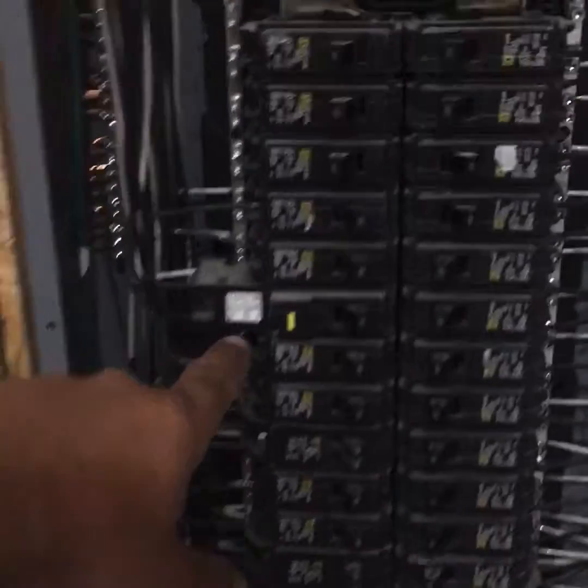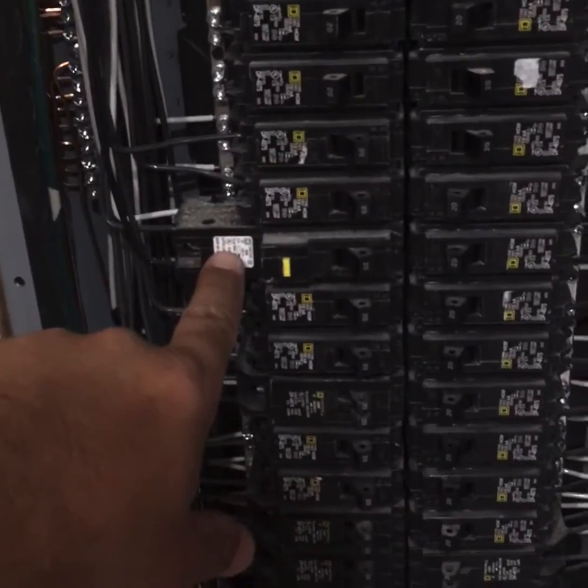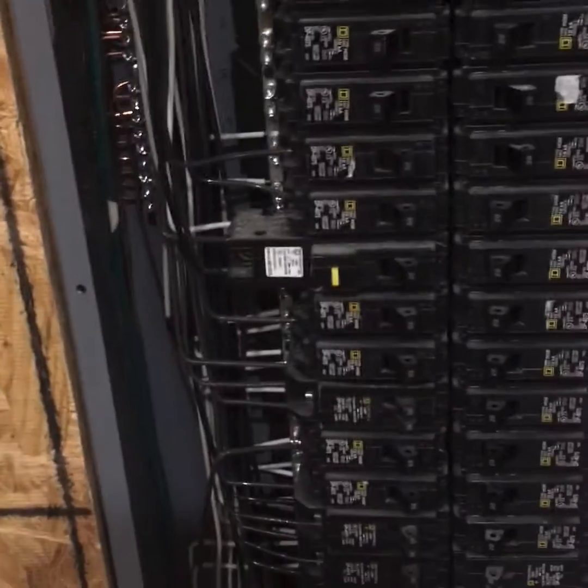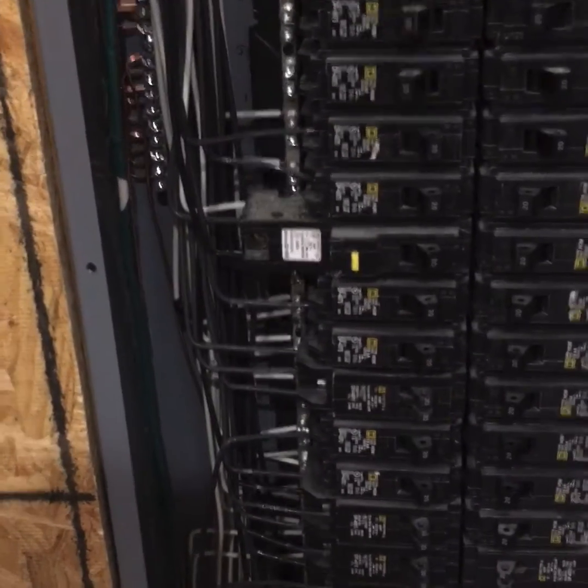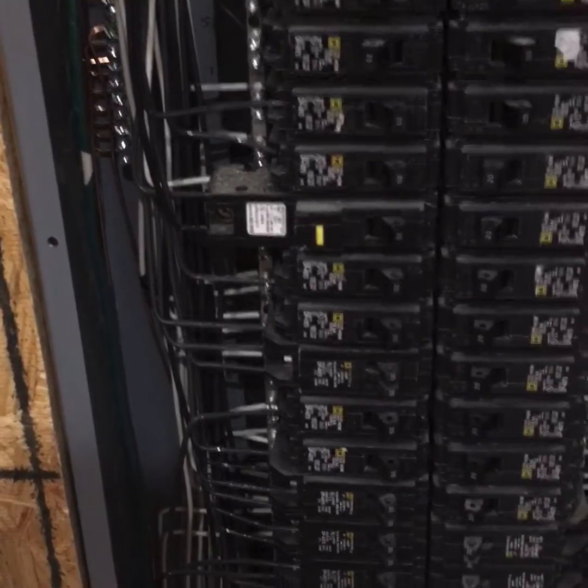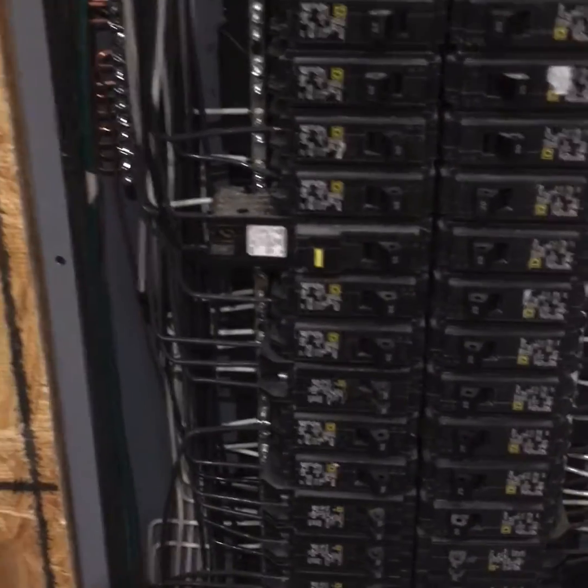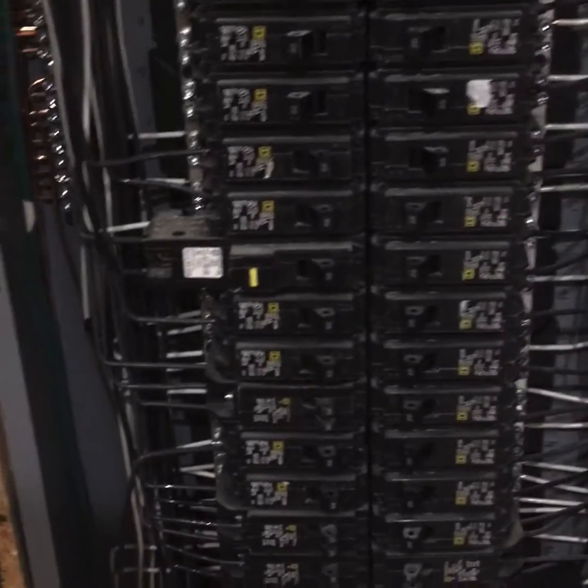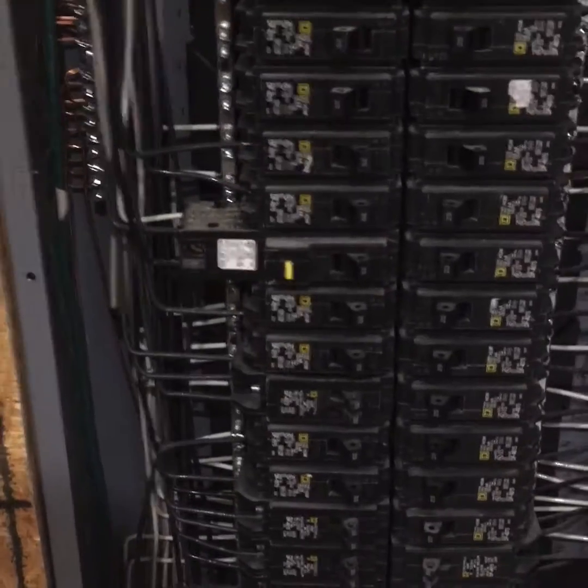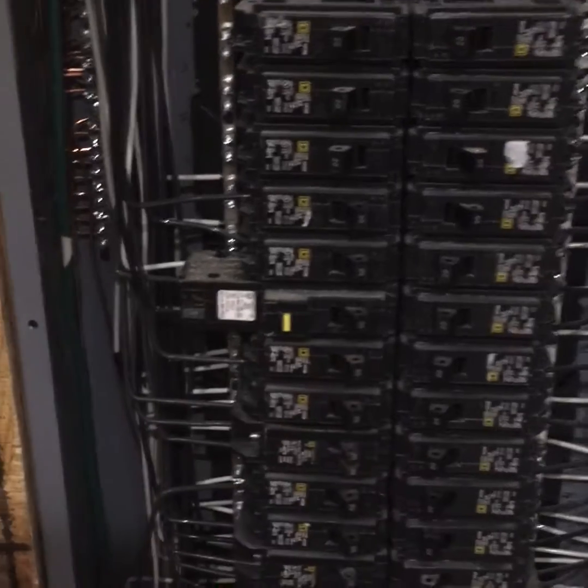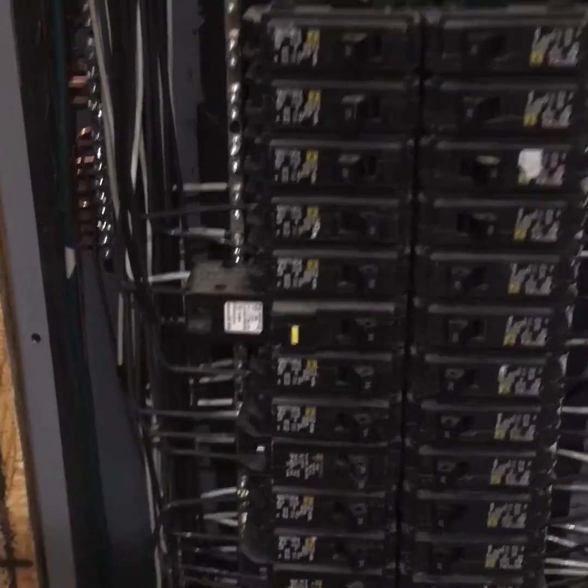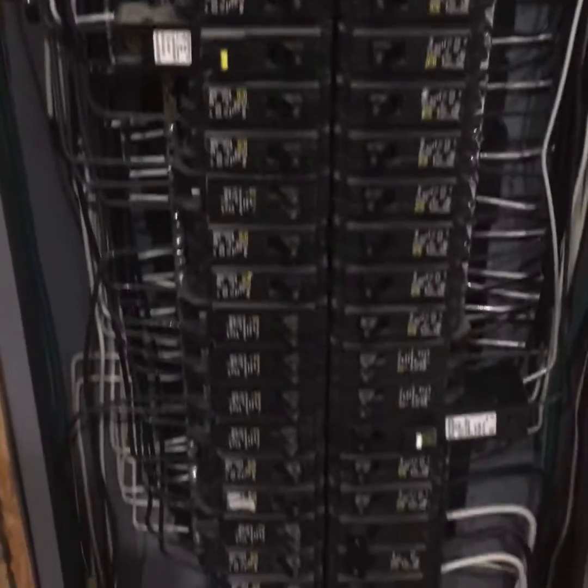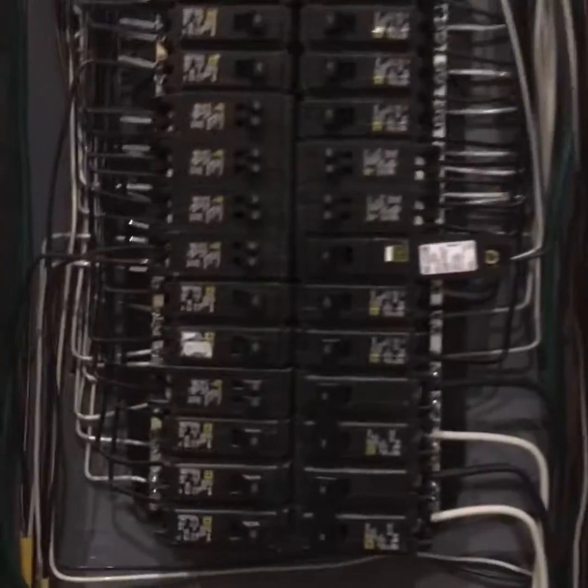Another thing I do is I have a GFI breaker here. That goes to all of my exterior plugs. I think there's only 4 on this building. It's not a real big building. I don't like putting GFIs on the exterior, even the watertight, weatherproof, whatever GFIs. They're a maintenance nightmare. I've got one GFI breaker protecting all of those plugs. If there's a problem, they can come in here and flip that breaker. Arc fault right there goes to my CO2 detectors. They are not part of the fire alarm system. They're standalone. And that's really it.